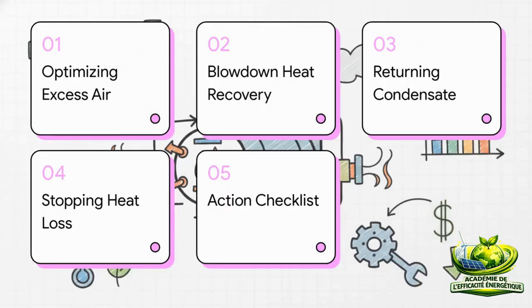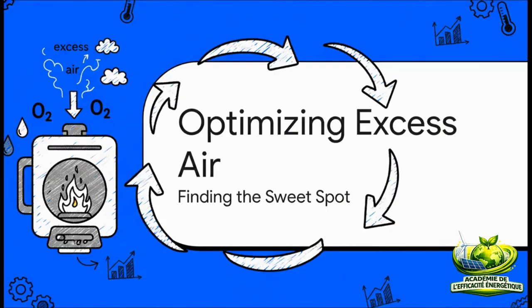Well, we're going to break this hidden boiler money down into 4 optimization zones: tweaking your excess air, capturing blowdown heat, returning your condensate, and stopping distribution heat loss. And at the end, I'll give you a super practical 5-point action checklist to get you started. All right, let's jump straight into Zone 1, optimizing excess air.